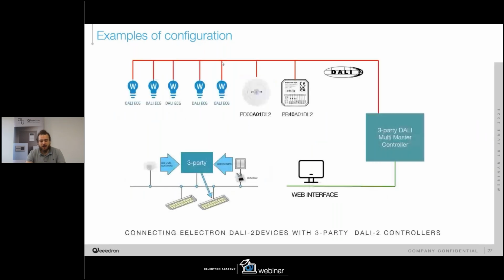Another example of configuration, don't forget that our system is a DALI2 system that is a standard. This means that if in your project you are looking for a push button interface or a presence detector like our multi-sensor presence detector, you can use our sensor inside the DALI bus generated and controlled by another gateway or another DALI controller. So since we are compatible with DALI2, our sensor and push button interface will be compatible also with third-party applications based on DALI2.